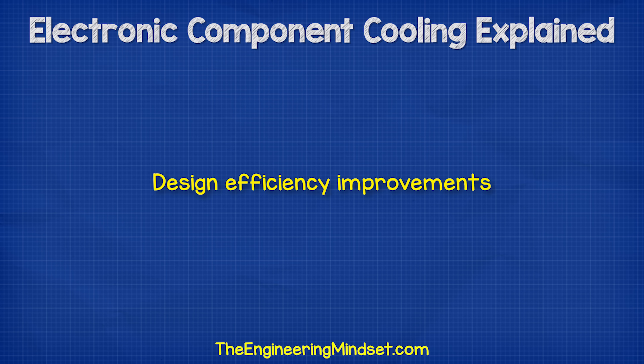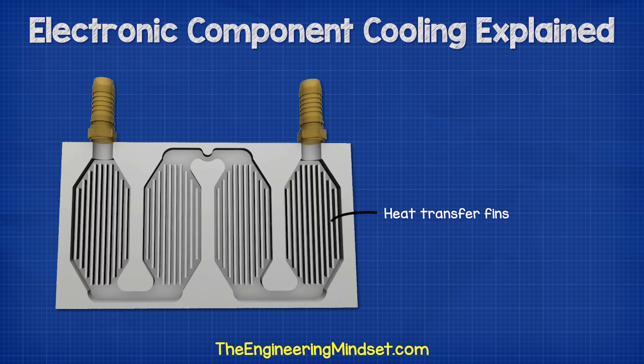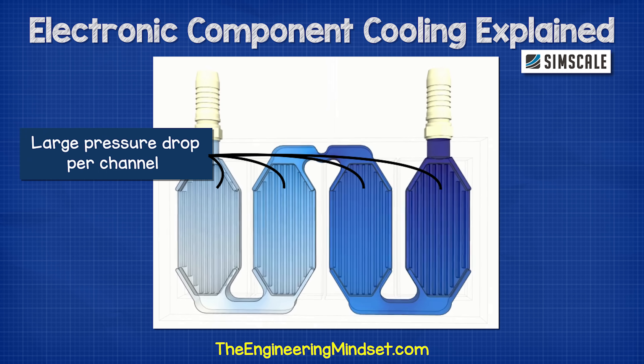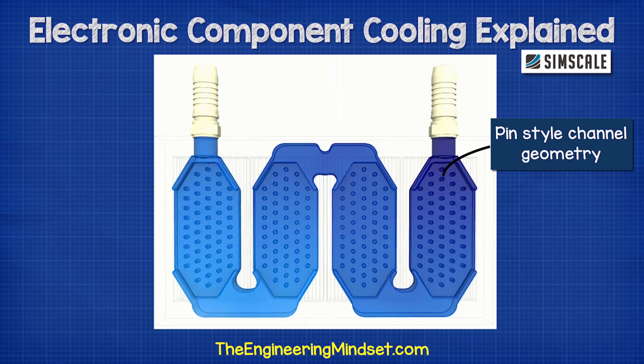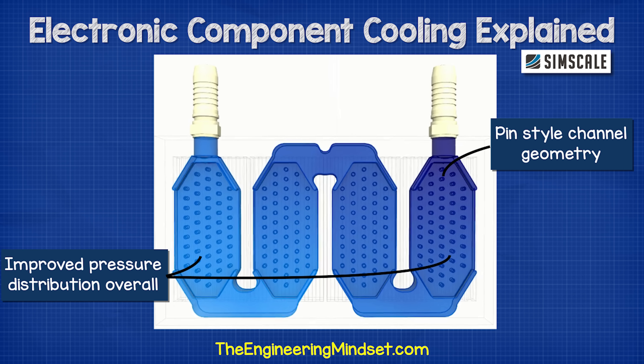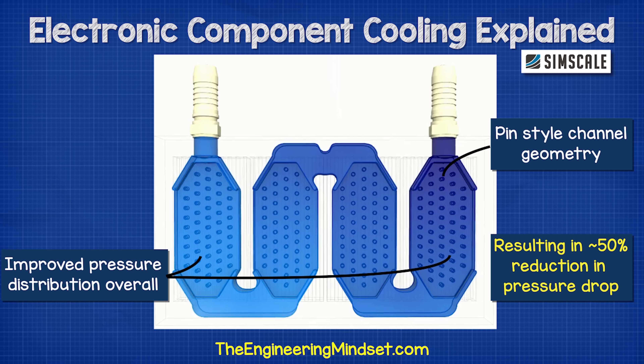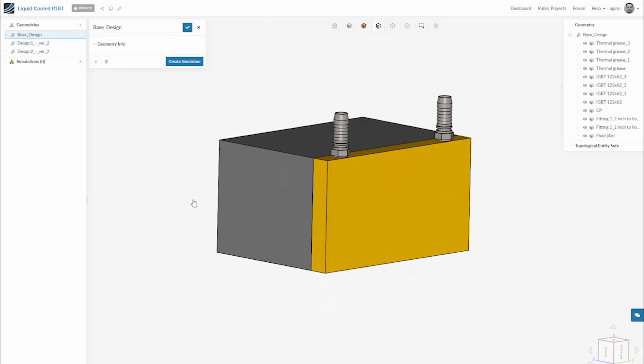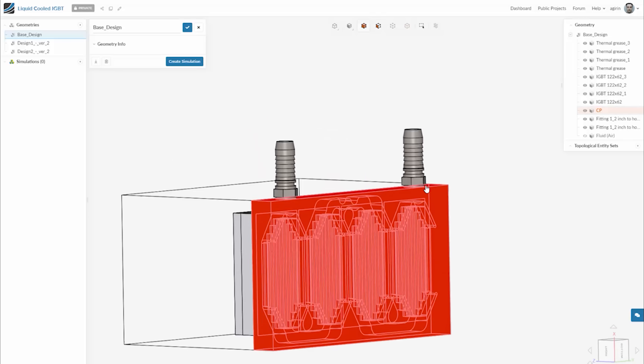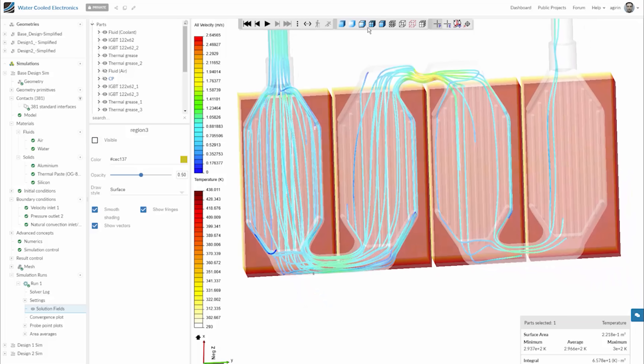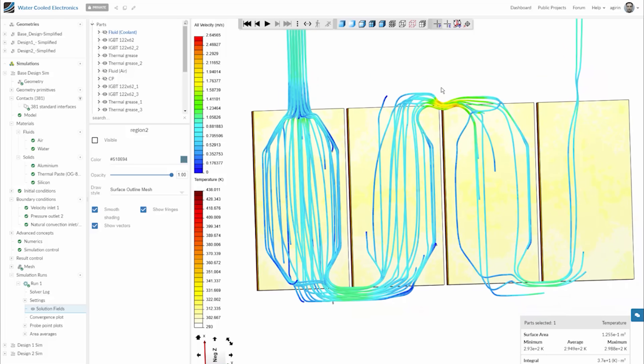Now the next step is to improve the efficiency of our design. The original design has these fins running through the heat exchanger, which help to expose the water to the heat of the IGBTs. However, we can see that this design causes a high pressure drop in each channel. The pressure drop of each channel adds to the pressure drop of the next channel, so overall the pressure drop across the unit is very large. Instead, we're going to use a pin-style channel. When we run the simulation for this design, we see a much more even pressure distribution across each of the channels and a lower pressure differential across the entire unit, leading to improved cooling performance and lower operating costs.